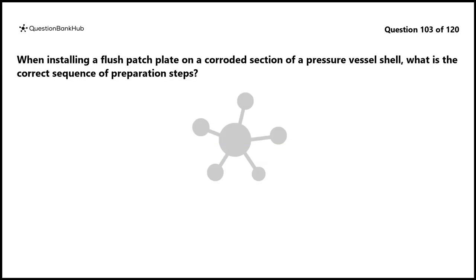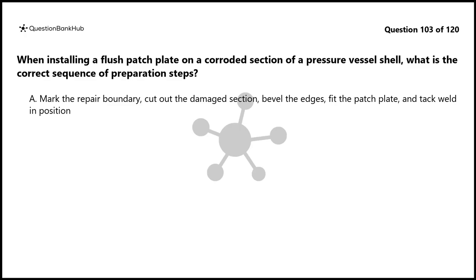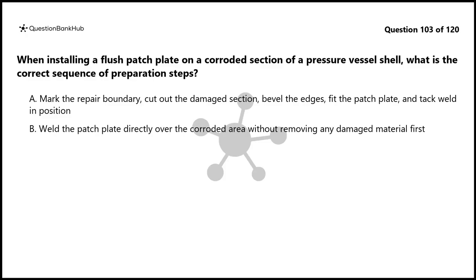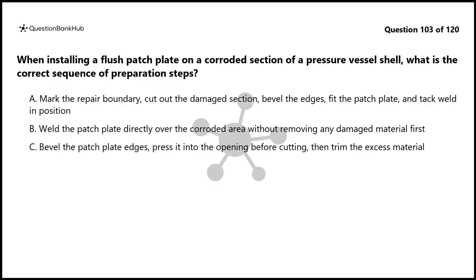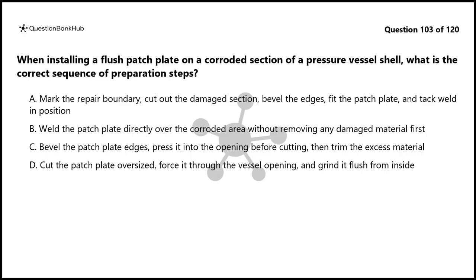Question 103. When installing a flush patch plate on a corroded section of a pressure vessel shell, what is the correct sequence of preparation steps? A. Mark the repair boundary, cut out the damaged section, bevel the edges, fit the patch plate, and tack weld in position. B. Weld the patch plate directly over the corroded area without removing any damaged material first. C. Bevel the patch plate edges, press it into the opening before cutting, then trim the excess material. D. Cut the patch plate oversized, force it through the vessel opening, and grind it flush from inside.